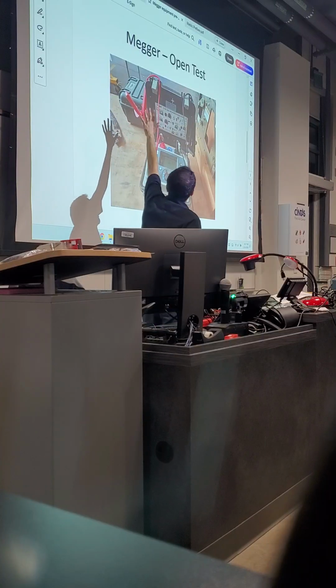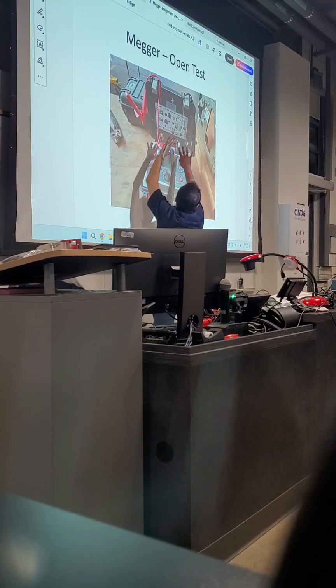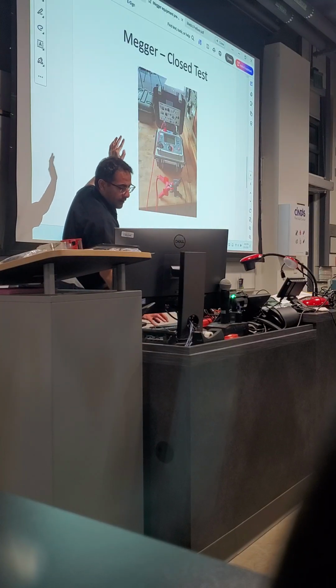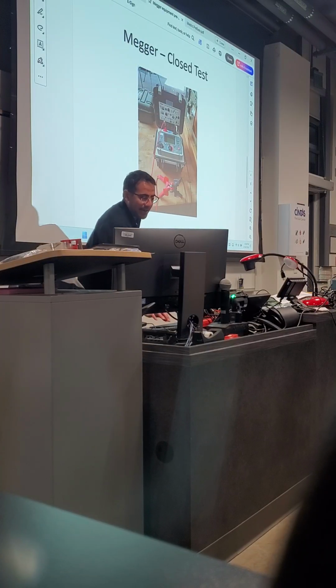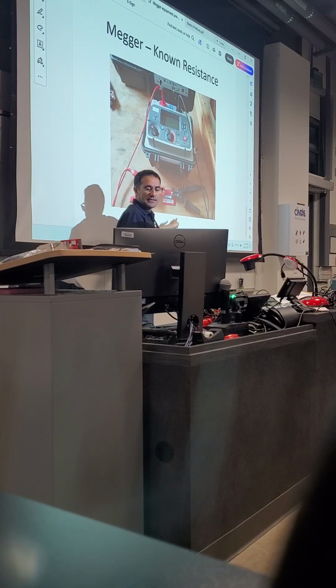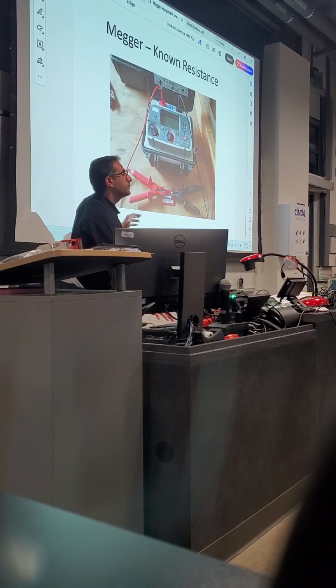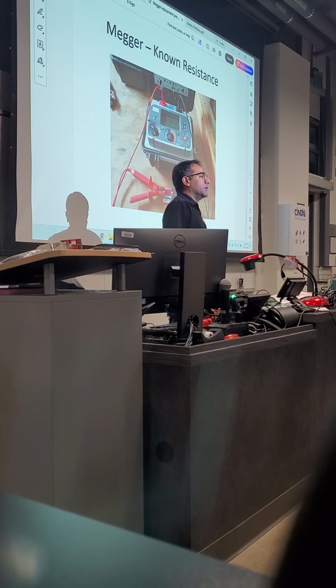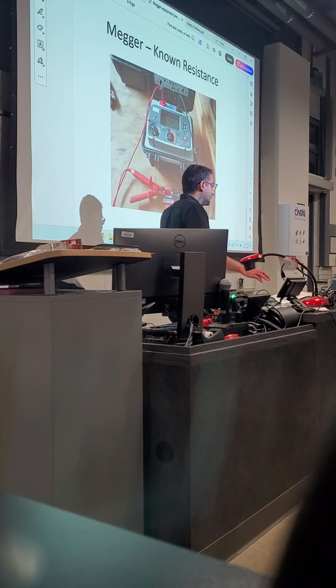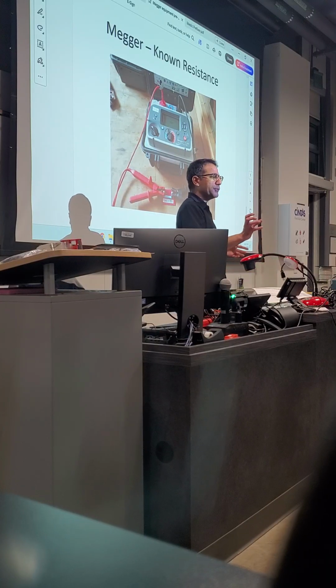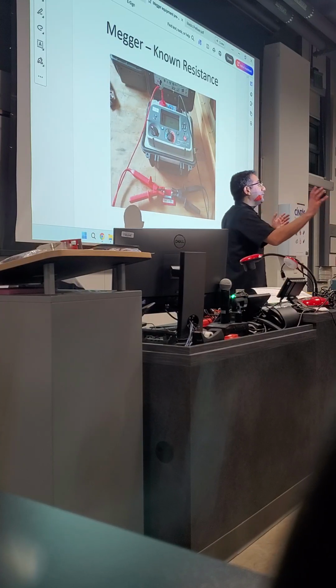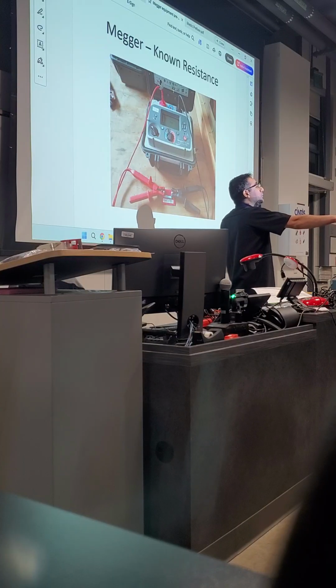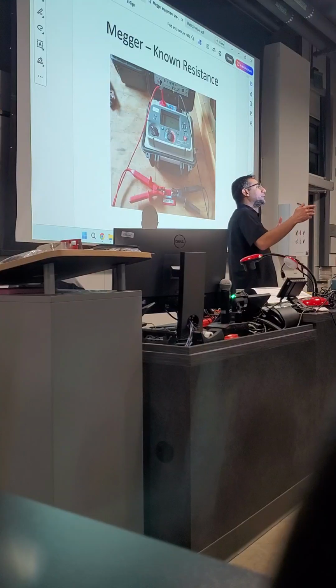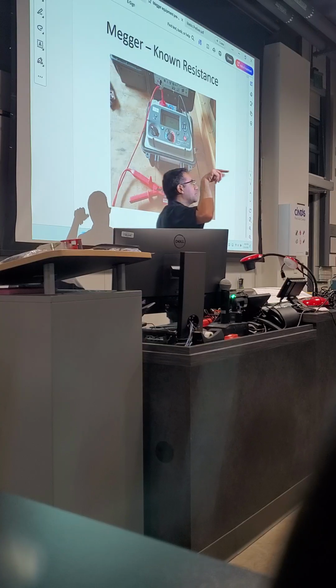So run the test, and what we're gonna be doing for the rest of the session is the pre-checks. So for the pre-checks, this is the visual. The leads are isolated. That's the open. This is short. The second pre-check and the last electrical pre-check is against the known resistance value. Questions? Where should we have our voltage at? It depends on the equipment that you're testing. So let's use the breaker as a reference. If you are testing this breaker, follow the reference voltage for this one. If you are testing a high voltage breaker, follow the reference voltage for that one. So for the purpose of pre-checks, use this molded case breaker, 600 volt.